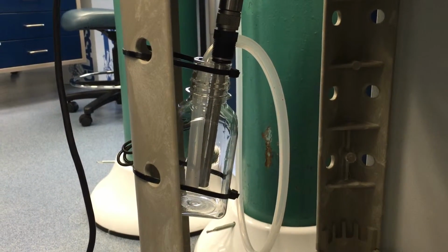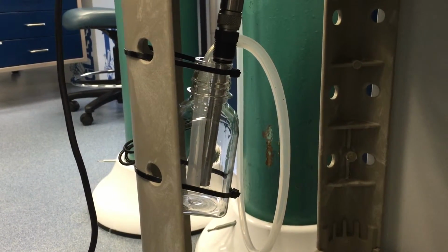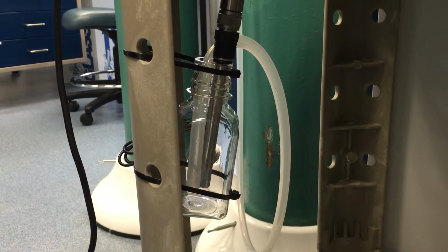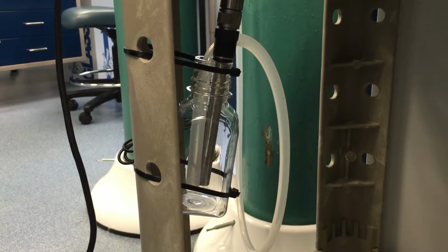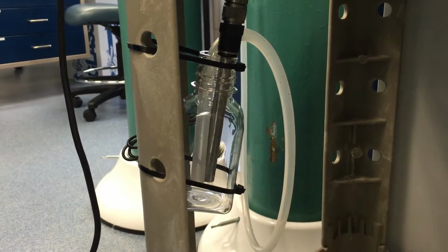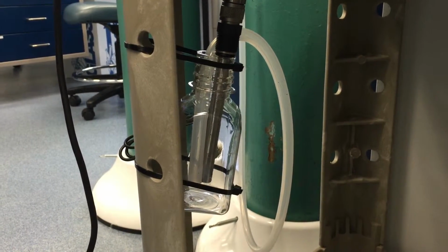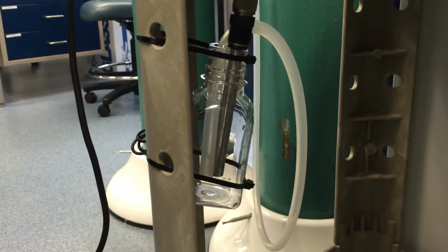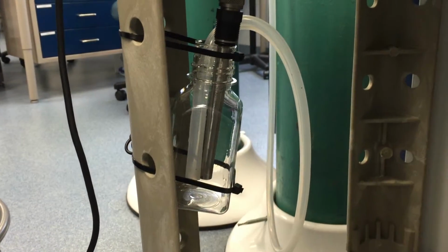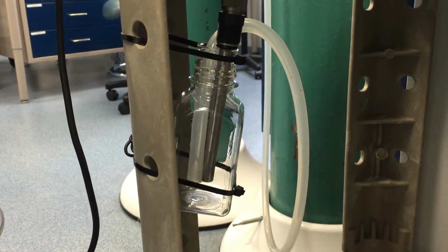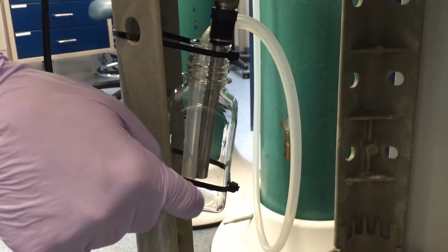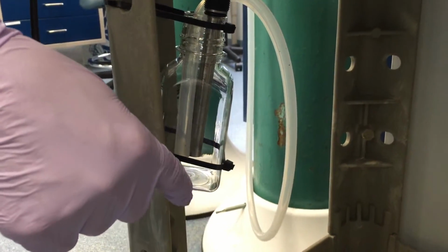Okay, so I'm going to show you the way that we do the zero calibration. There are two things that are kind of tricks that are not explained in the manual. One is the way that the probe and the tubing are placed in the calibration bottle, and the second is the actual calibration itself.